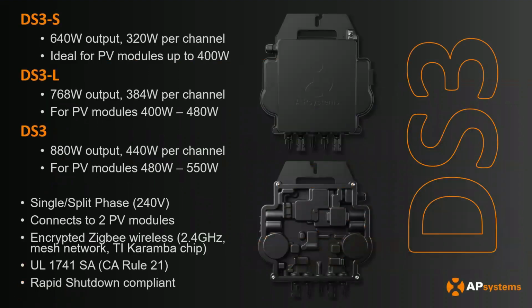It comes in 3 flavors, the first 2 being the most popular, just because the DS3 without any initial at the end is extremely powerful. The first one is the DS3-S at 640 watts. It's ideal for PV modules up to about 400 watts. The DS3-L comes in at 768, so it's good for PV modules 400 to 480. All of the PV module sizing really depends on your preferred AC to DC ratio. Here for these numbers, we used about 1.25, so depending on your preferred oversizing, it may adjust. And then the DS3 at 880 watts is for higher powered modules. We're not typically seeing that used in residential, like the S and the L.